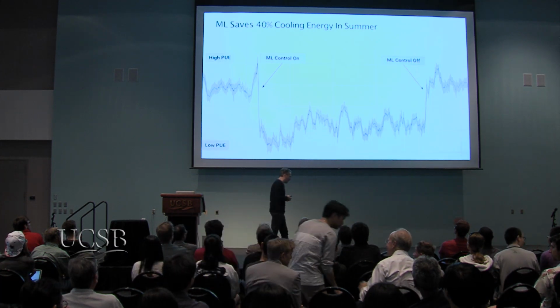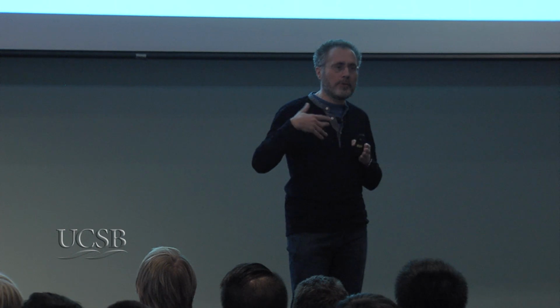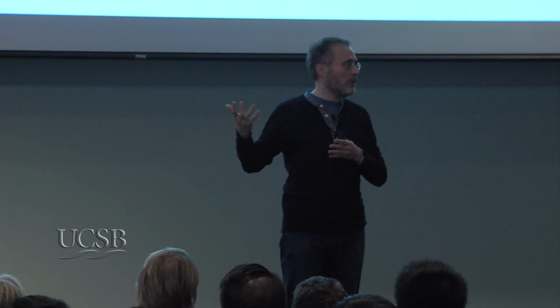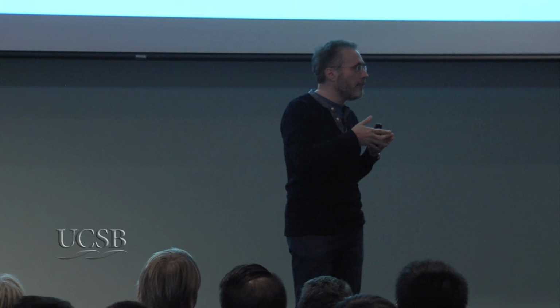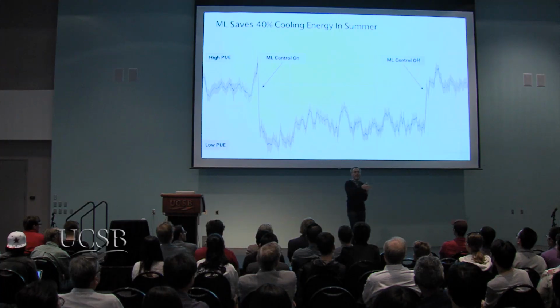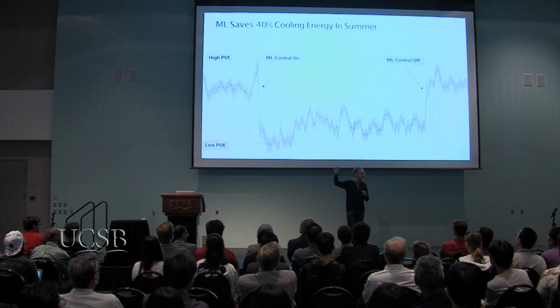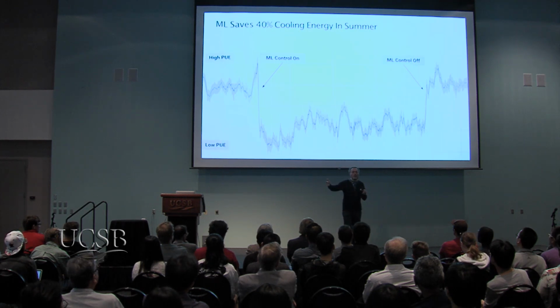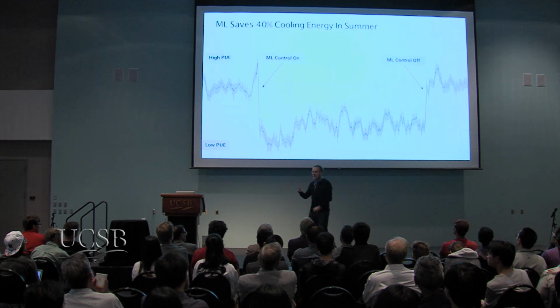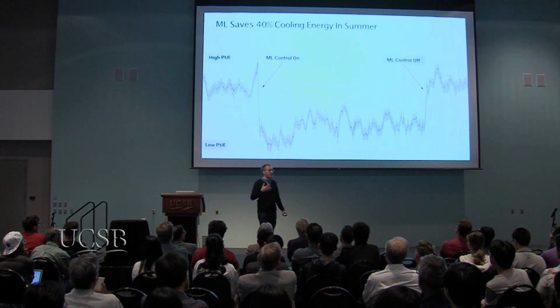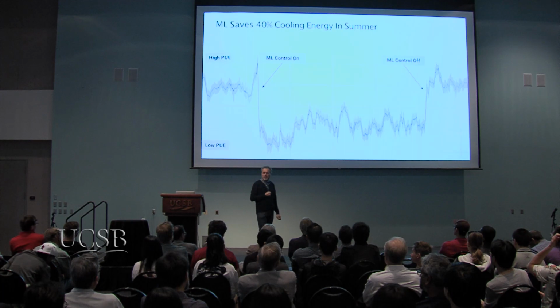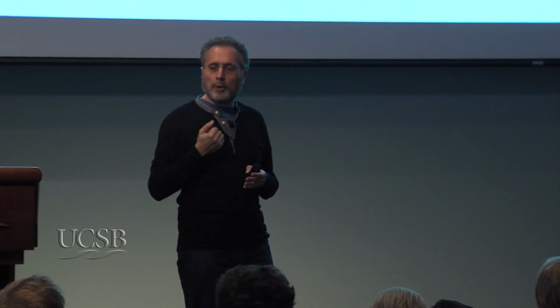So what's happening here is that we took a building and fed all its parameters into the cloud for machine learning - every few seconds, things like pump speed, fan speed, outside temperature, the load on the data center floor, and of course all the energy overhead metrics. So the machine learning system had as inputs a lot of historic data points for that building, plus what the cooling overhead was.